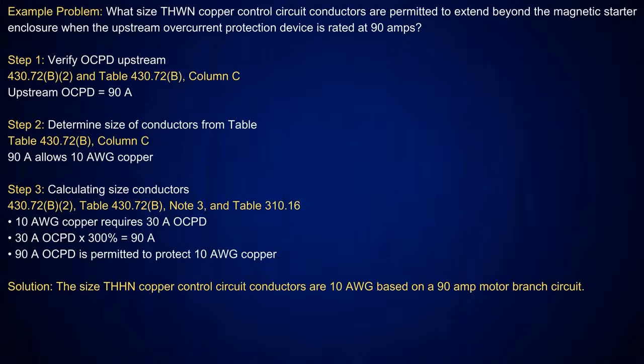But look at this. Now I'm going over there. I'm not in free air open space going over there. So now I have to use table 310.16. And it's going to tell you in note 3 to apply 300% on it. Well, if I look at a number 10 copper conductor, it's good for 30 amps. I take that at 300%, gives me 90 amps, and it tells you, therefore, 90 amp could protect what? Number 10 conductors. So it's proven the point there.